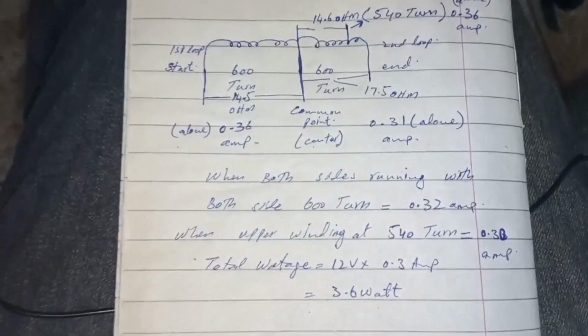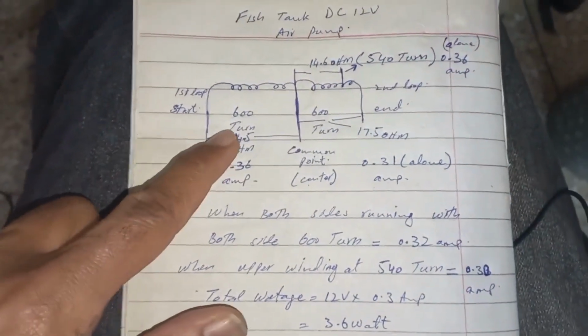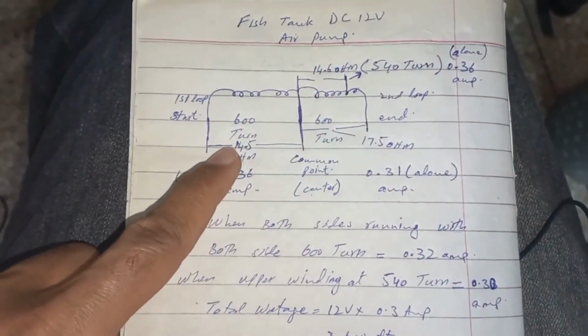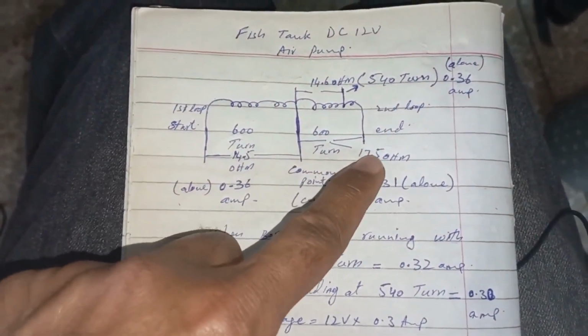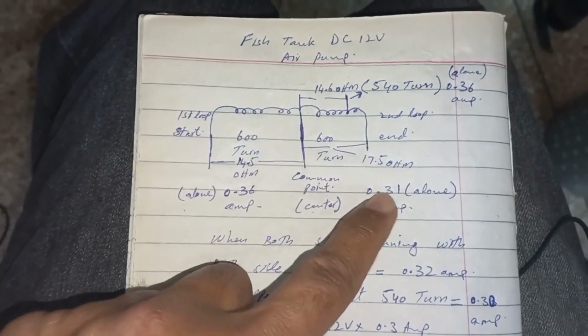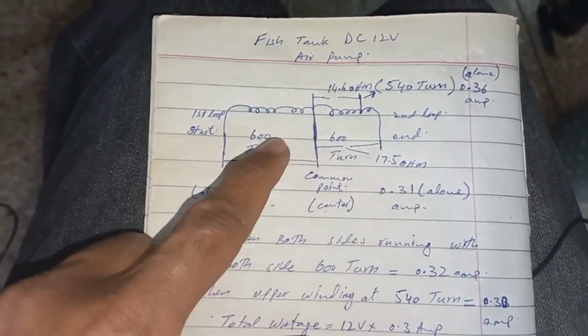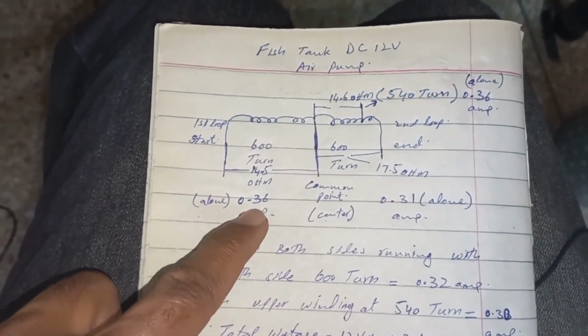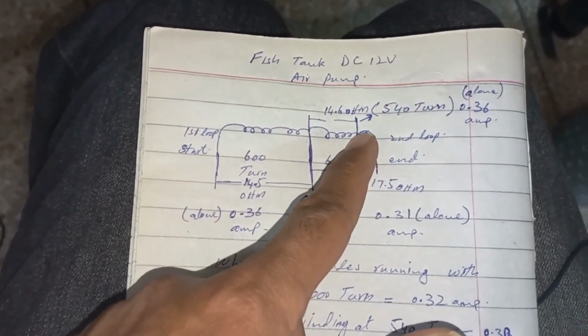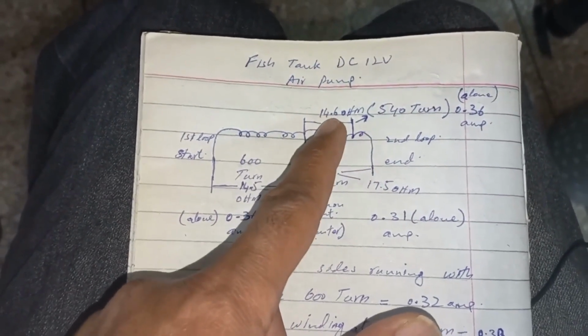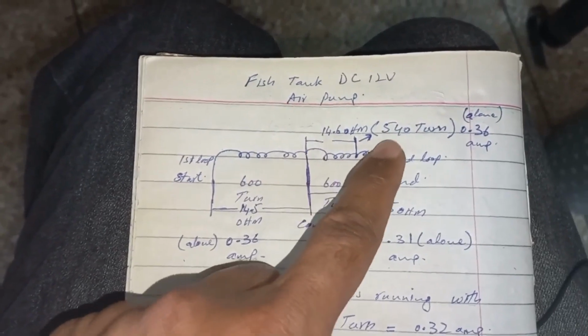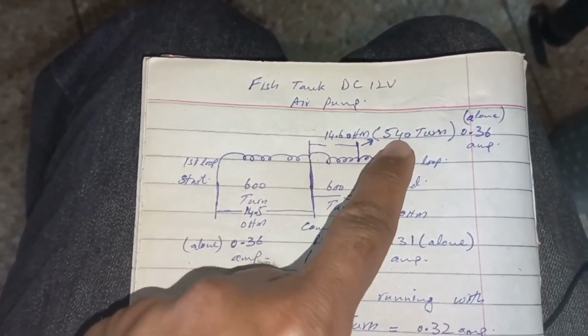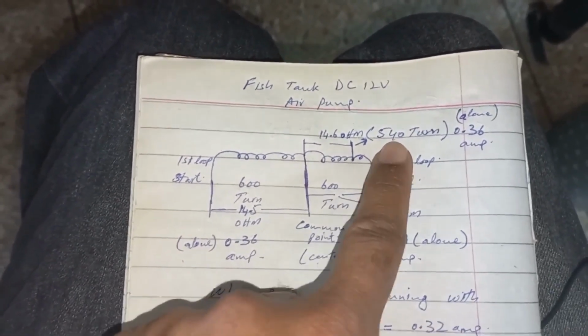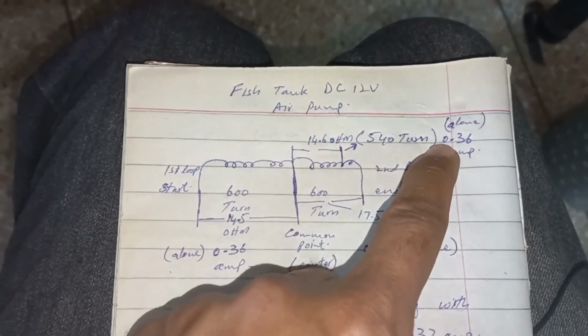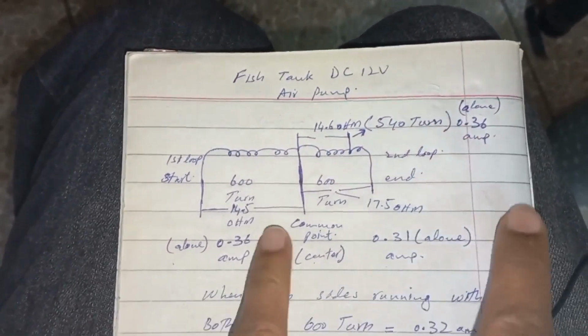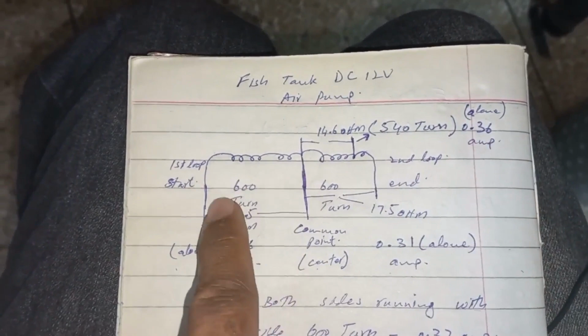Here is the summary of the turn ratio. Before, it was 600 and 600 turns, and the resistance was 14.5 and 17.5 ohm. Here the current was 0.31 amps and here the current was 0.36 amps. So I take out the loop from here, 14.6 ohm. This loop I have taken out approximately 540 turns, and at this loop the current alone was 0.36, very close to the first one.